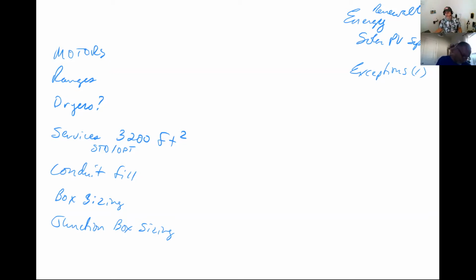So this table is pretty simple. Remember, this is only for the service, not a branch circuit. With branch circuits, every branch circuit has to match up with whatever is on that branch, so there's no diversification - I have to count the full value. But when I start adding things up on a feeder, there's a chance not everything is on at the same time or at the same operating capacity, so we call that diversification. This table has a diversity factor, which is what these percentages represent. The more dryers we throw in on a service, the less we calculate any one individual dryer - the more dryers we have, the lower that percentage is.